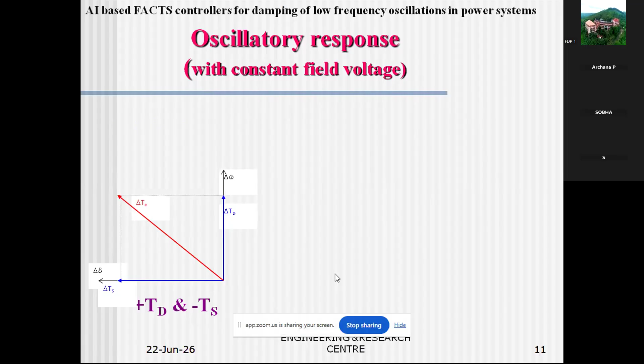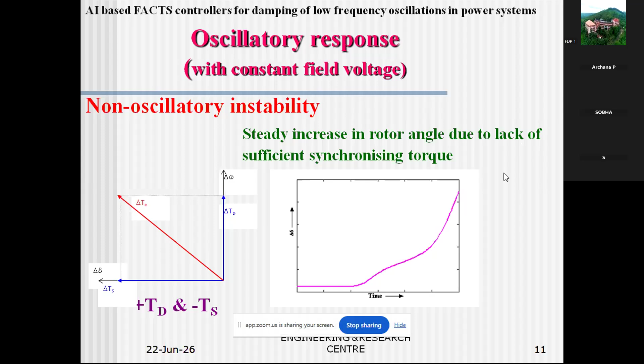This happens mostly when there is no AVR and the system is carrying a lot of power flow and is connected to a weak grid, that is, the short circuit ratio is very small. Under those conditions, there is always a threat to the synchronizing torque and the system may go unstable without any oscillations, without any oscillatory mode. But fortunately, almost all systems are now working with automatic voltage regulators. So there is not much threat of this type of non-oscillatory instability. But more frequently, we are having oscillatory instability.